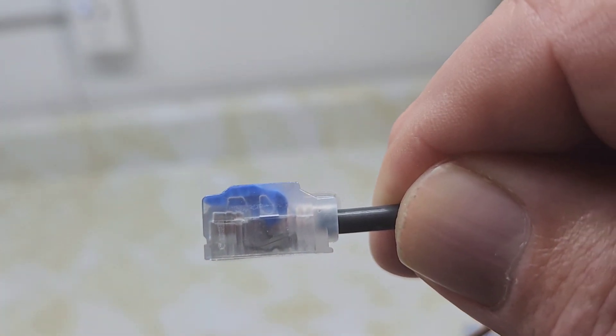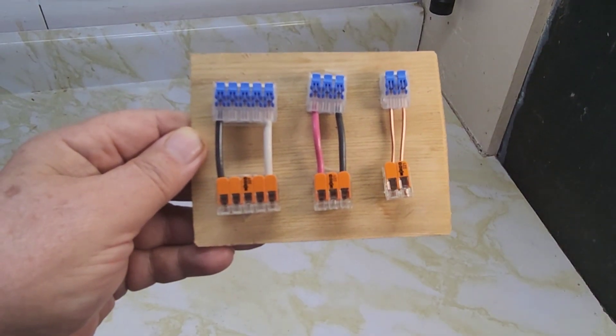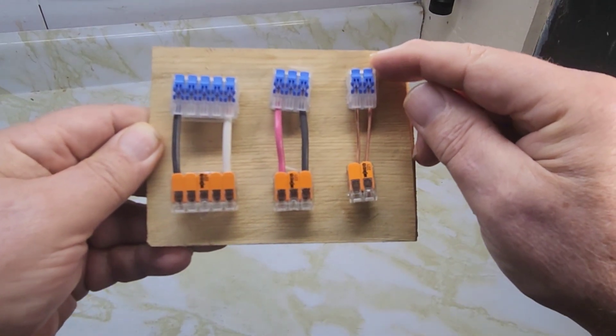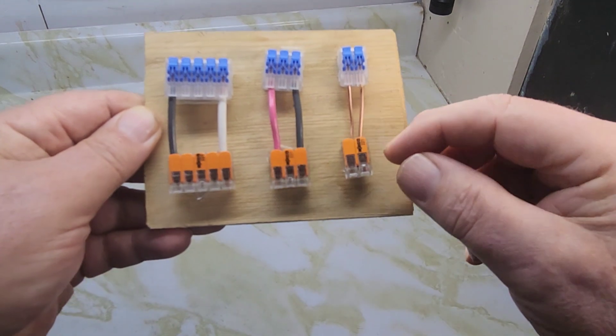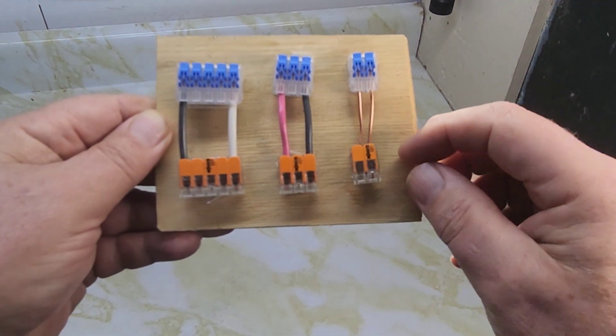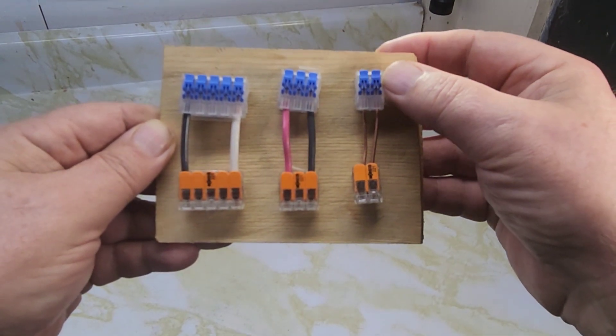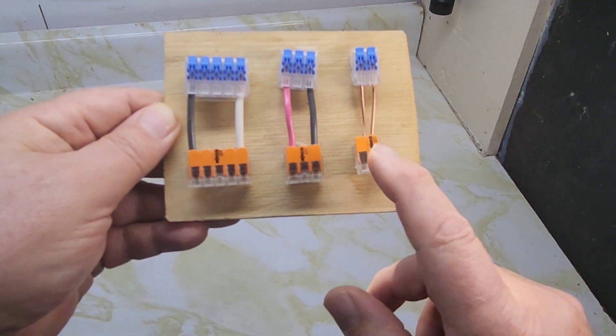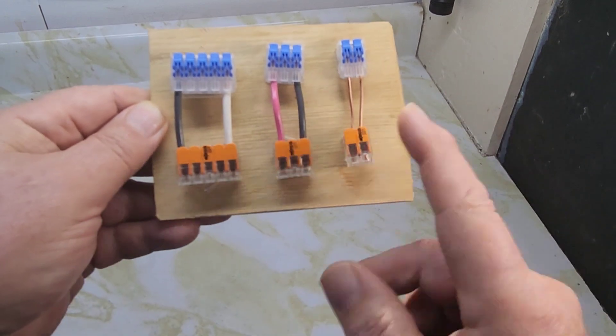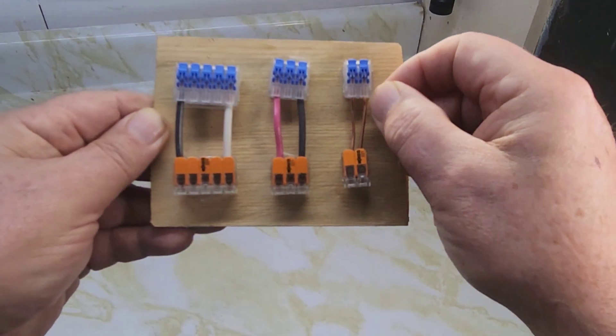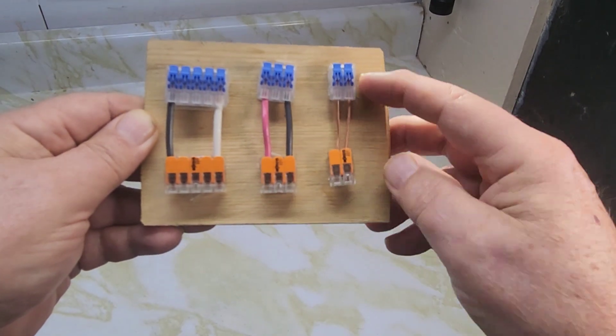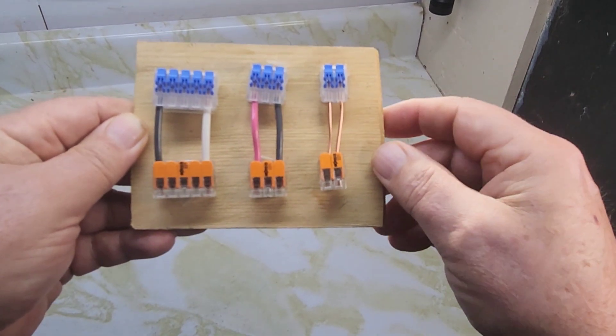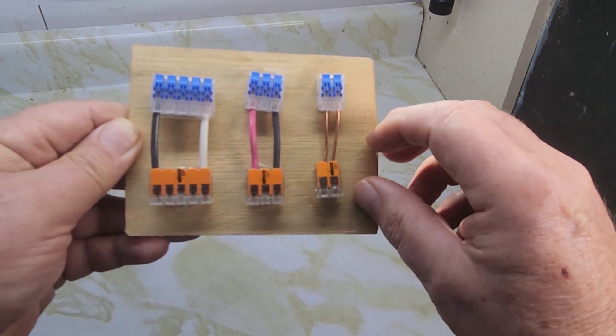Today we checked the Ideal connectors compared to the Wago connectors. The Ideal has the wire going on this side and the lever on the opposite side. The Wago ones, people are saying that sometimes they'll flip up when you put them in the electrical box. The Ideal ones are a little bit different - they actually snap down, so less chance of them flipping up. As far as the Wago one goes, I've had no problems whatsoever with these. If you're not sure they're going to flip up, just tape them with electrical tape. The Ideal ones, you just press the 12 and 14 wire inside - you don't even have to toggle the lever up. The Wago ones, you have to open up and put the wires in. So put in your comments which one you prefer - the Wago or the Ideal. I will give the slight edge to the Ideal.